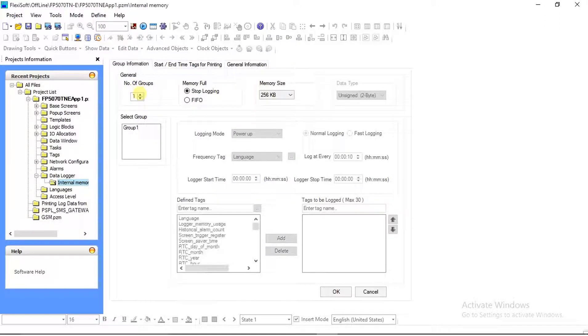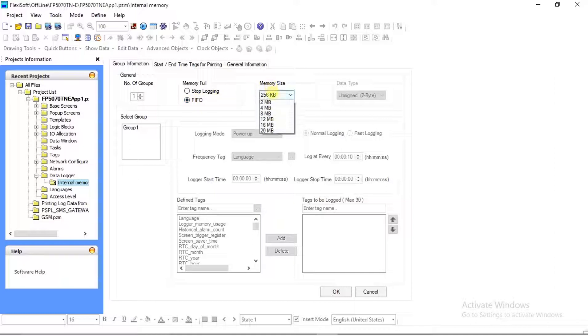Select the number of groups for data logging as per requirement. We will add only Group 1 for now. Here, after memory is full, the following action can be taken: Stop Logging or FIFO. We will select FIFO. We can also select the logger memory size as per the data logging requirement — here selecting 20 MB.